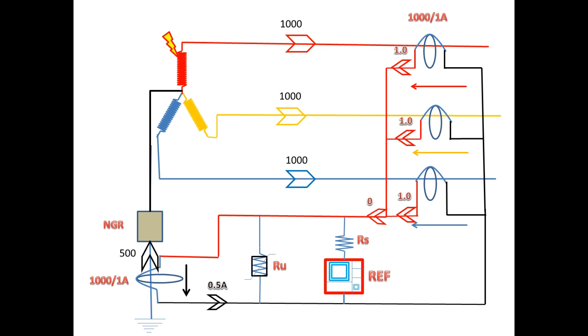Now let's see the current path. First, keep in mind that current always tries to take the lowest resistance path. Now we consider the current trying to flow outside, that is through the core balance CT. On the core balance CT, all three phase secondary CTs are carrying 1 amp each, and there is no unbalanced current.